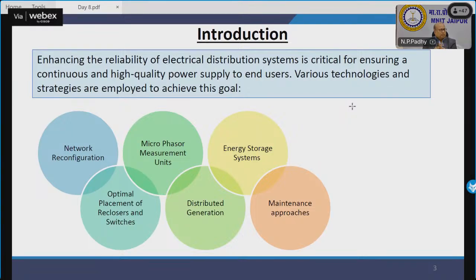You know what phasor measurement equipment is? In the transmission system, we get voltage, frequency and phasor stamping values at each moment, because in a smart grid environment you measure voltage at a particular point and then take a control action assuming that value holds. But by the time you've taken a control action, the voltage might have changed. So through a micro phasor measurement unit in the distribution network, if I measure that data, it is as exact as possible, and the time delay can be reduced.